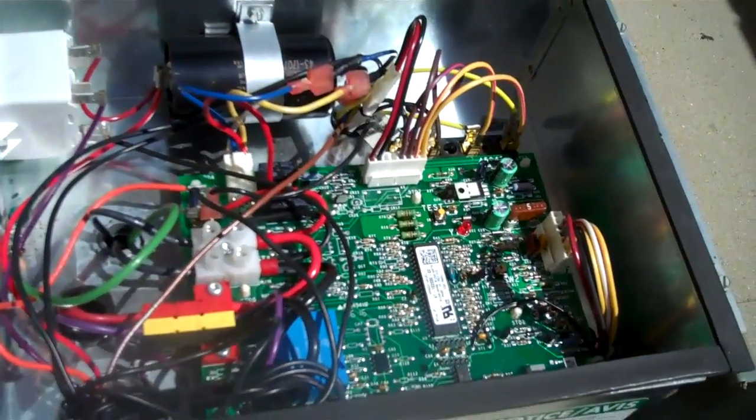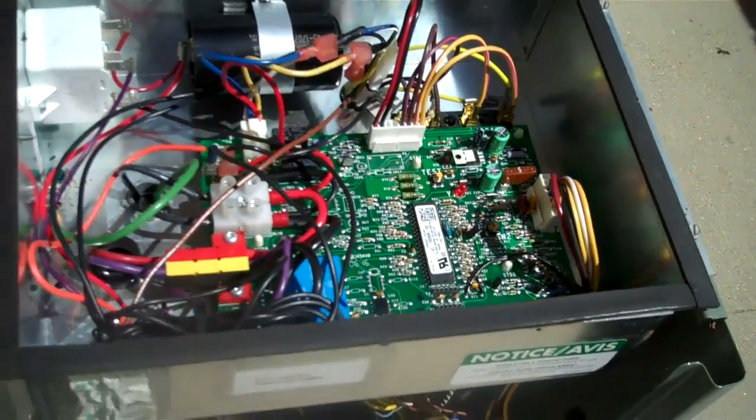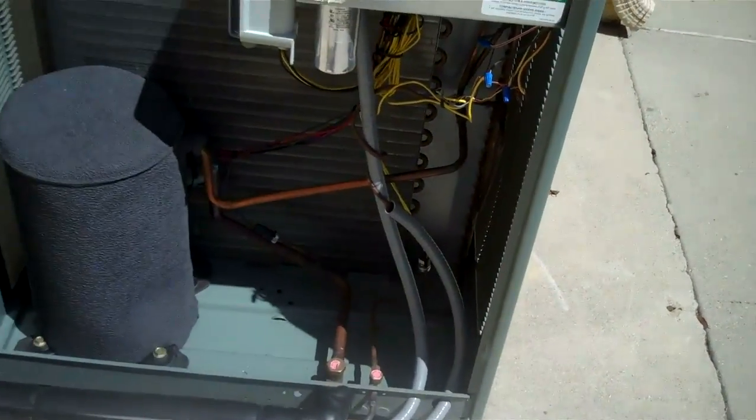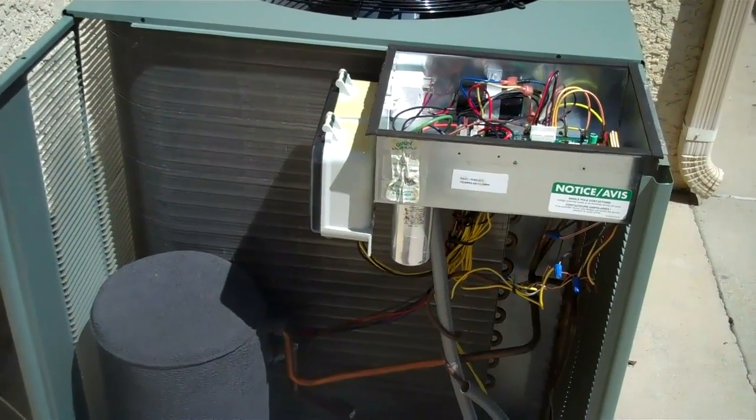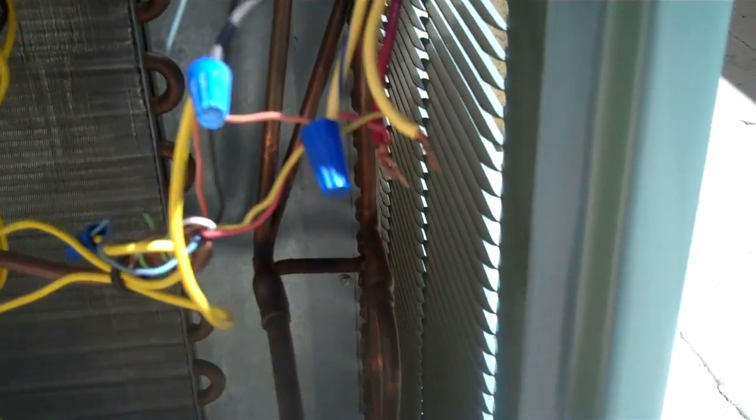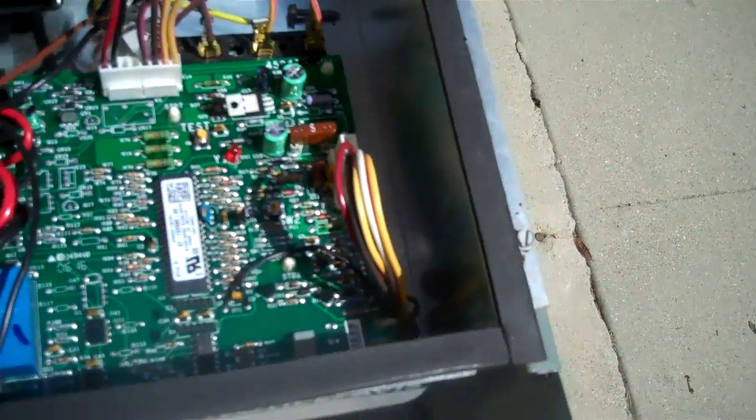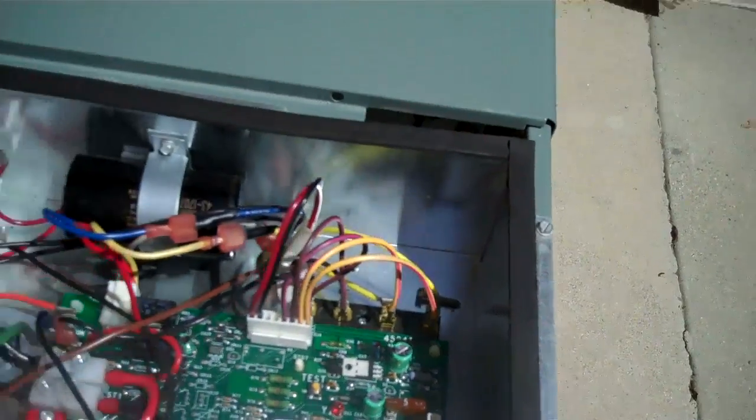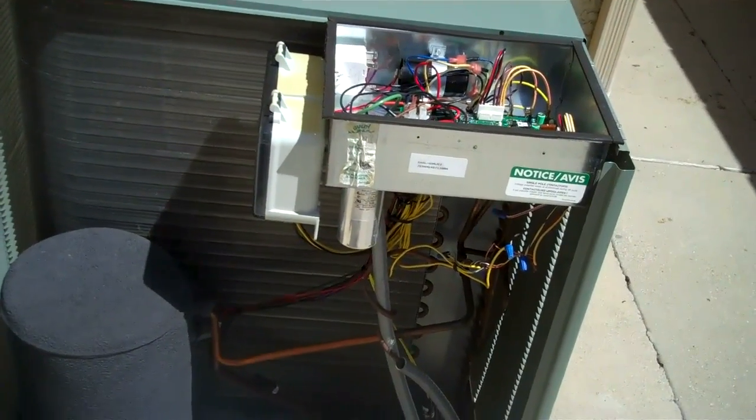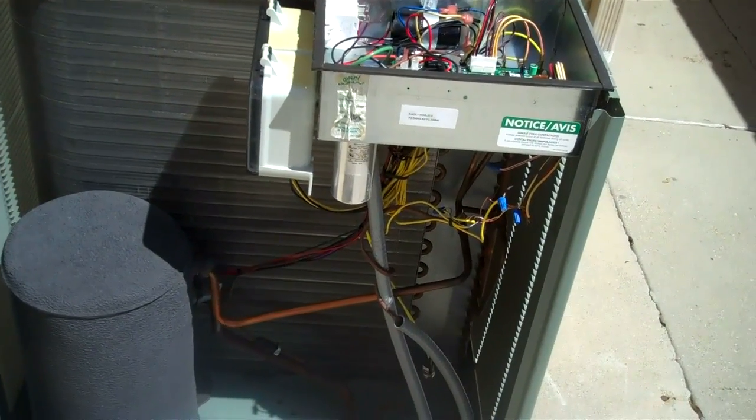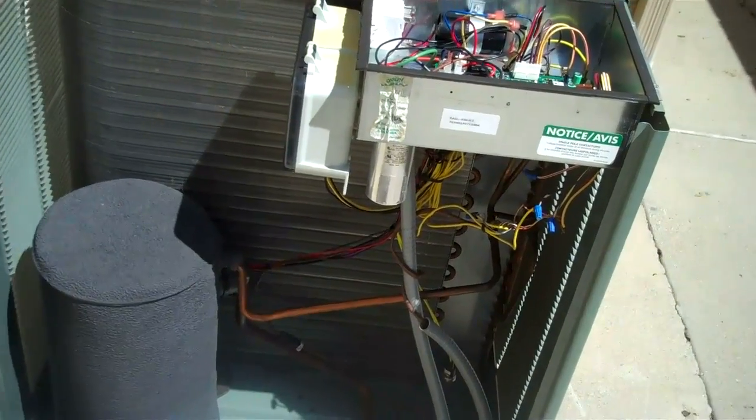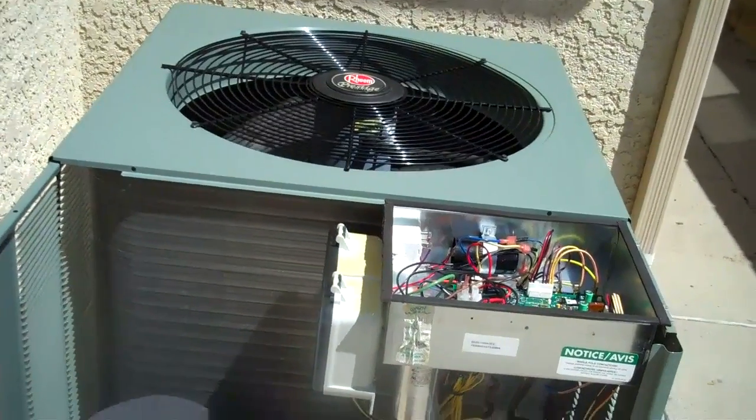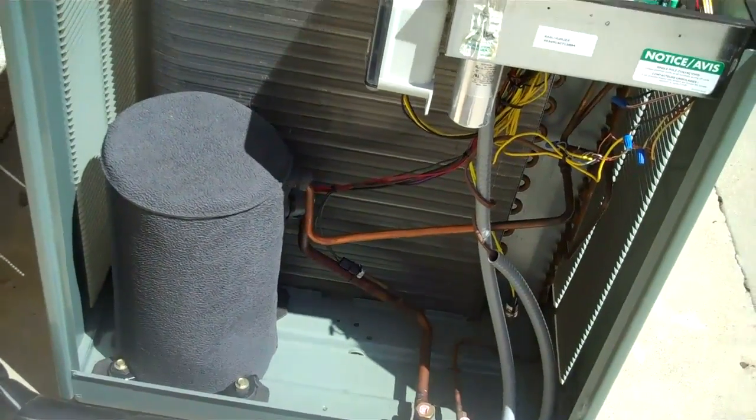Okay, so here's the unit, you know, it has the board, you know, it looks pretty sophisticated, so you come out on a service call, the customer left, you can't get in the house, he says it blows fine, I just have no cool air. One thing you can do to this, since I got my 24 volt wires coming here, you can jumper the R, the Y1, or Y2, it's actually going to pull in the fan on the indoor unit, and I can run my AC without turning on the thermostat. So inside right now, I got 24 going to the Y to the inside, which is going to pull that the furnace up on high speed, and I'm running in my air conditioning right now without going into the house, with the customer not being home. It's a little trick you can do.